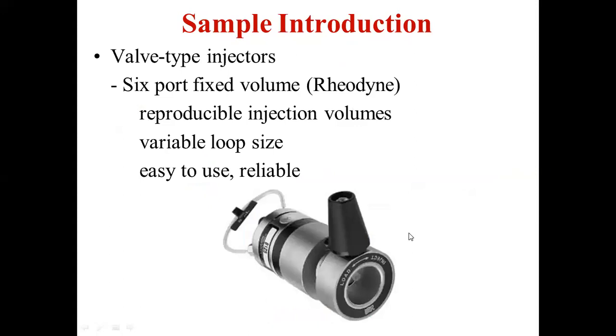And in order to introduce the sample, the injection system is very, very important. As we have discussed in gas chromatography, we will use loop injectors. By means of a hypodermic micro syringe, we can introduce the sample into the chromatographic column. So this is going to be the loop injector system, which is used in the HPLC instrument. You can see here load and inject, inject and load. This is a knob able to be rotated and moved.